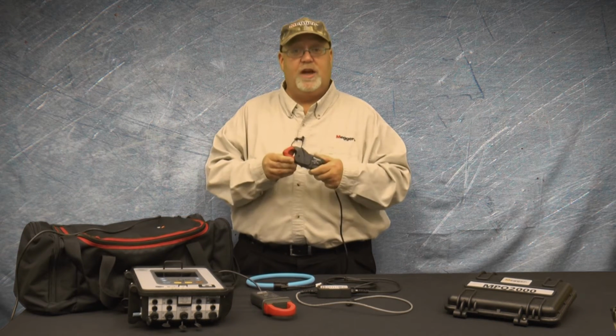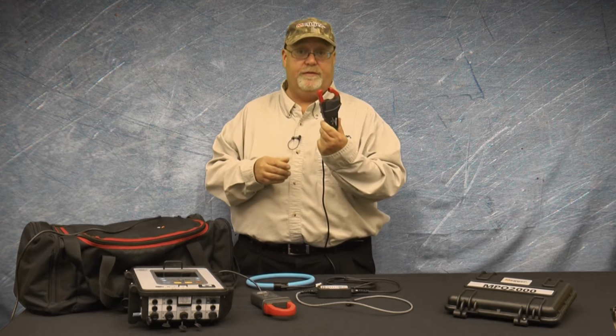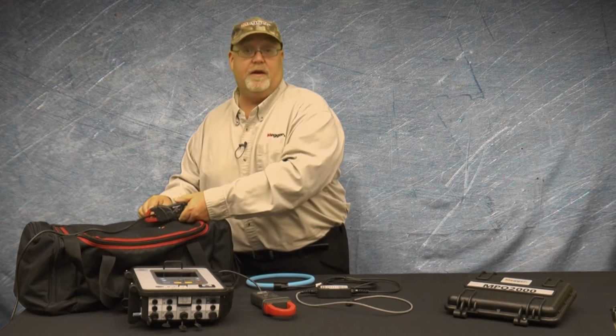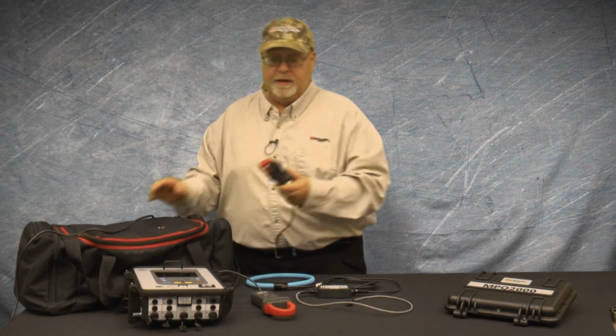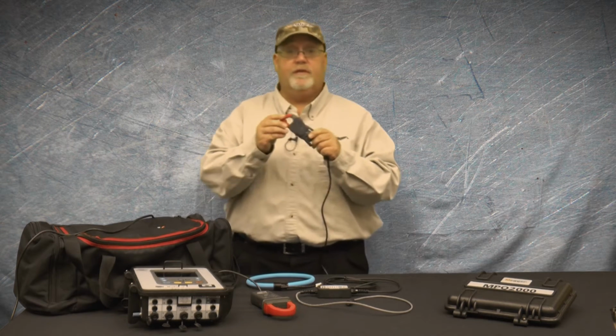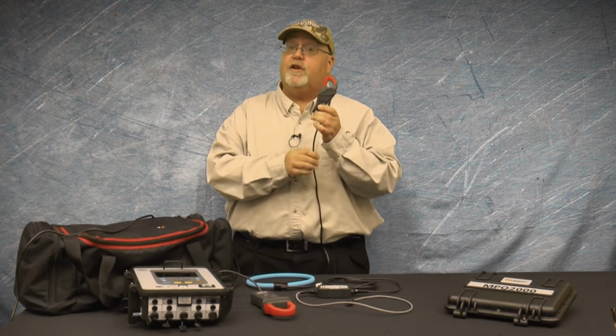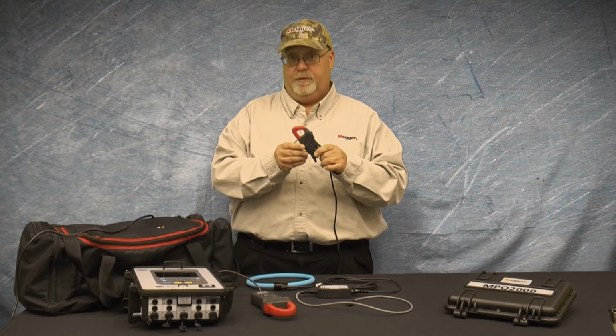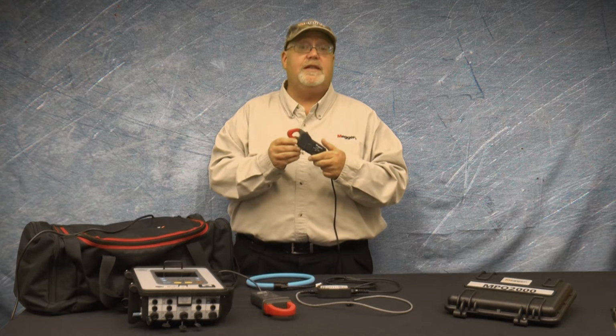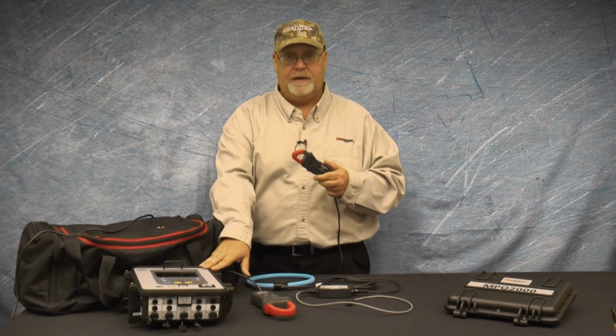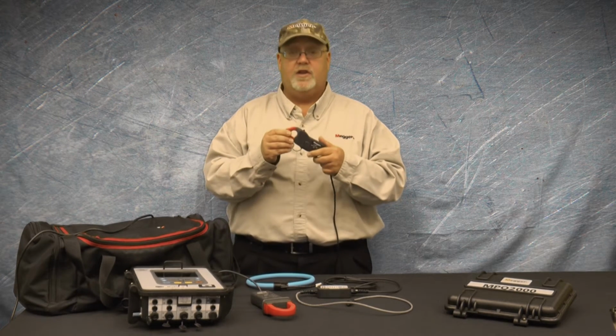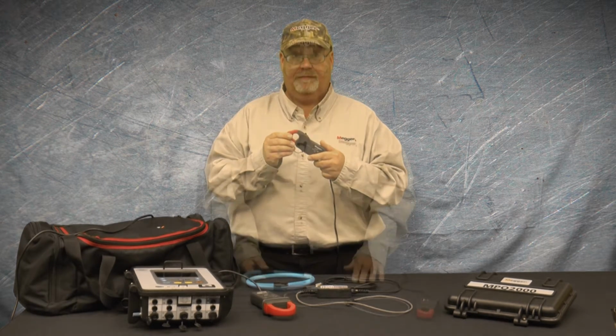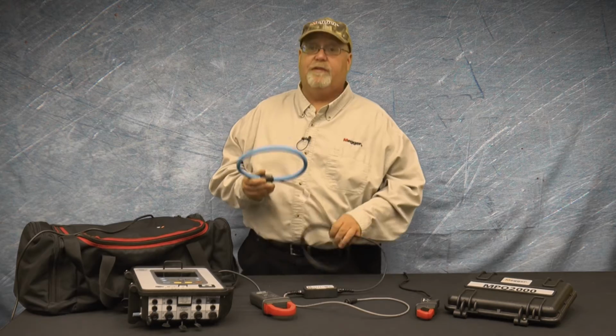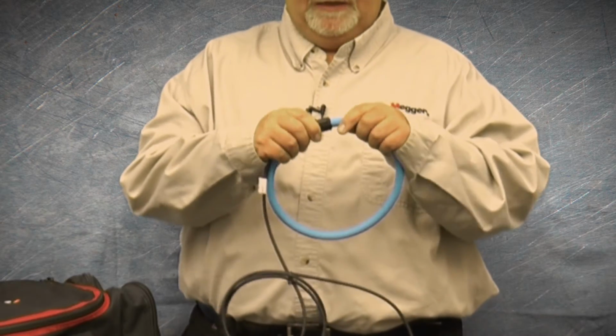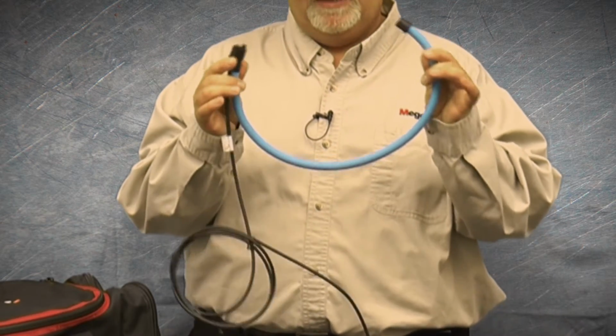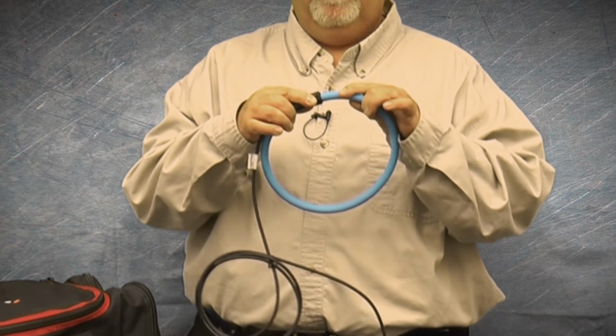As the name would suggest, the split core CT splits. This allows it to go around the wire that has to be tested. Now, the split core CT can have two different types of outputs. It can either have a current output or a voltage output. The split core CTs used with the Megger line of power quality instrumentation has a voltage output from 0 to 1 volt. The Rogowski coil, or flexible CT, is capable of being mounted around much larger cables and bus bars.